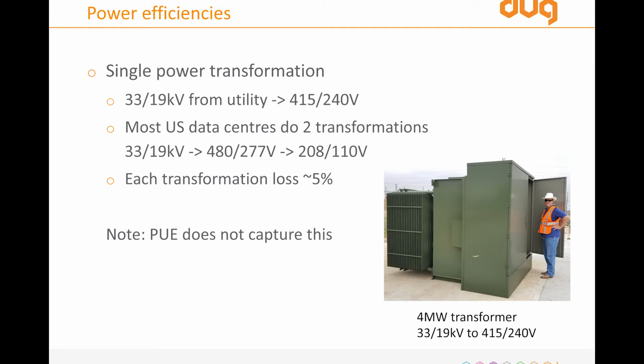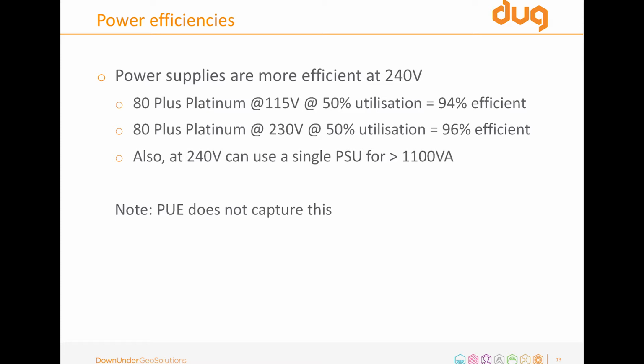The other thing which happens when you go to Australian power is your power supplies in your computer get more efficient. At 110 volts, the PSUs in your computer are only about 93% efficient, 94% efficient. At 240 volts, or 230 volts, depending on what statistics you use, they're about 96% efficient. So we gain 3% energy use just by moving to 240 volts. So we've gained 3 or 4% by having a single transformation, and we've gained another 3 or 4% just by going to 240 volts and having more efficient power supplies. That is not captured in PUE. Okay? That loss is actually on the positive side of PUE.